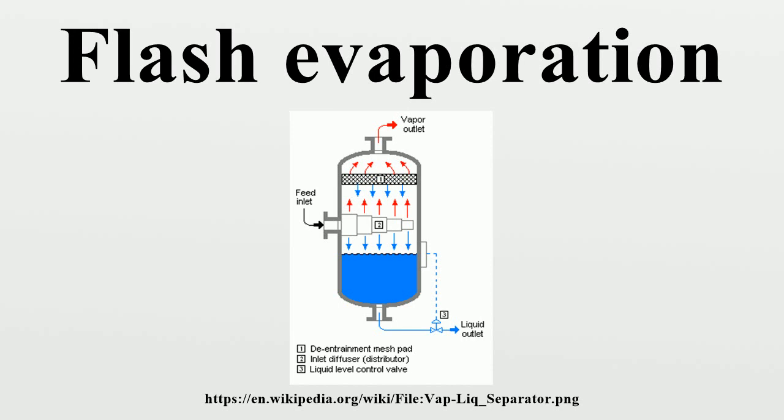This type of flash evaporation is used in the desalination of brackish water or ocean water by multistage flash distillation. The water is heated, and then routed into a reduced pressure flash evaporation stage, where some of the water flashes into steam. This steam is subsequently condensed into salt-free water. The residual salty liquid from that first stage is introduced into a second flash evaporation stage at a pressure lower than the first stage. More water is flashed into steam, which is also subsequently condensed into more salt-free water. This sequential use of multiple flash evaporation stages is continued until the design objectives of the system are met.